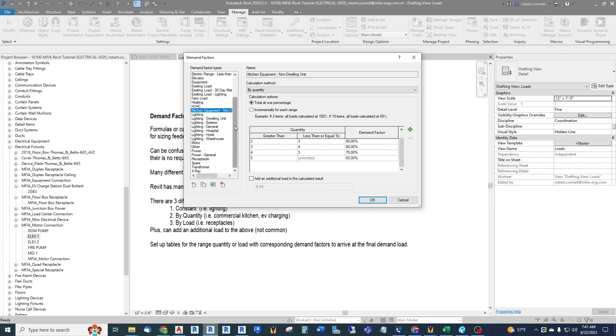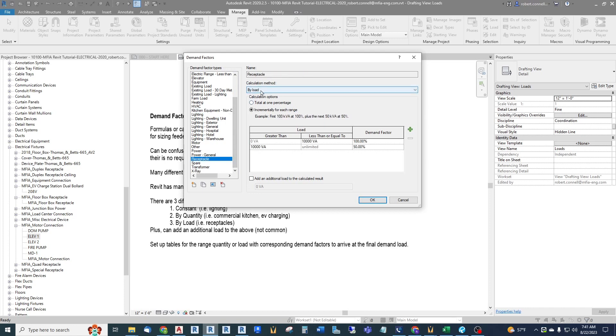The receptacle demand factor is done by load. For the first 10 kVA it's 100%, and anything greater than 10 kVA up to unlimited is at 50%. This incrementally adds loads based upon these levels and demand factors. So the first 10 kVA of receptacle load gets calculated at full value, and everything above that is halved.